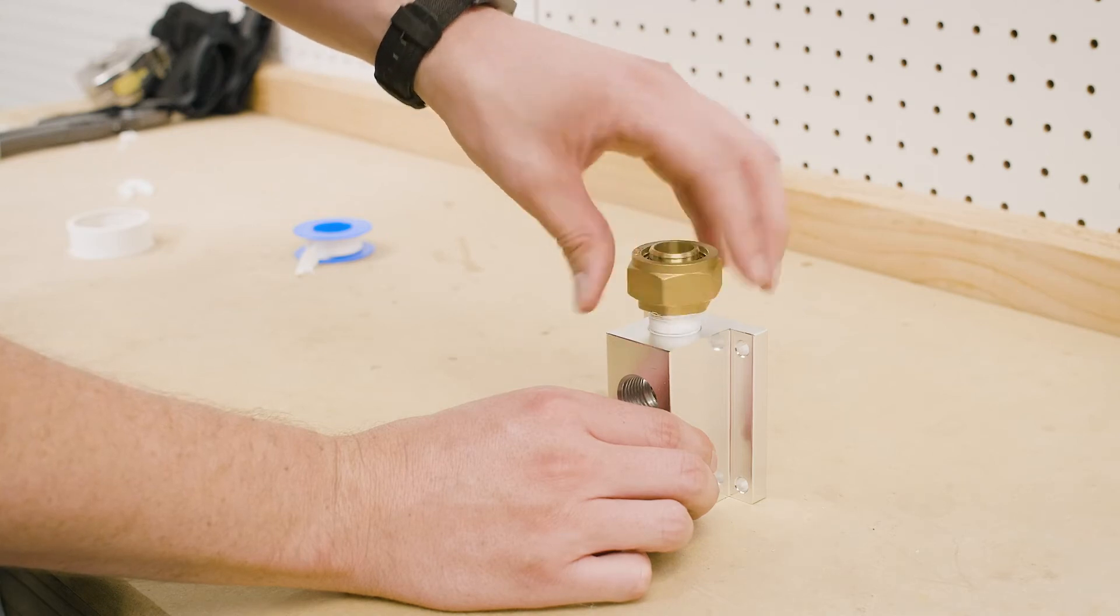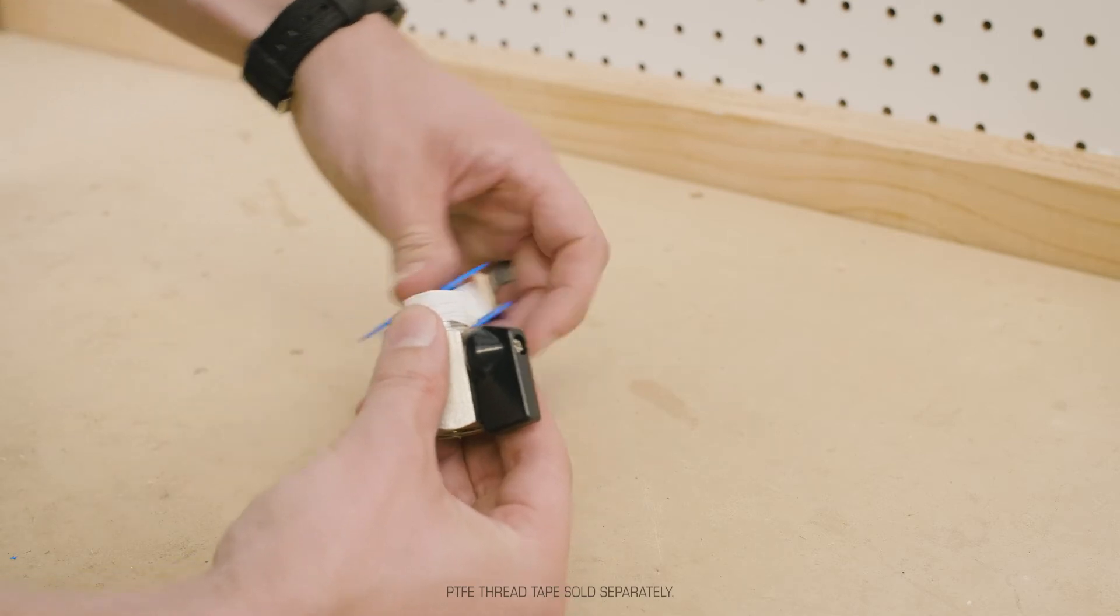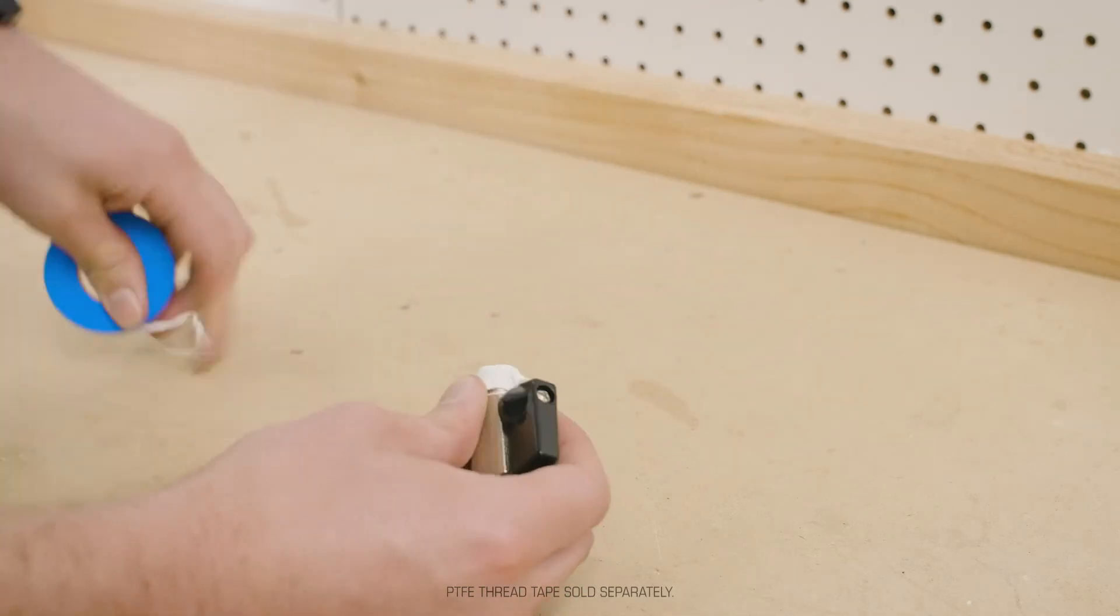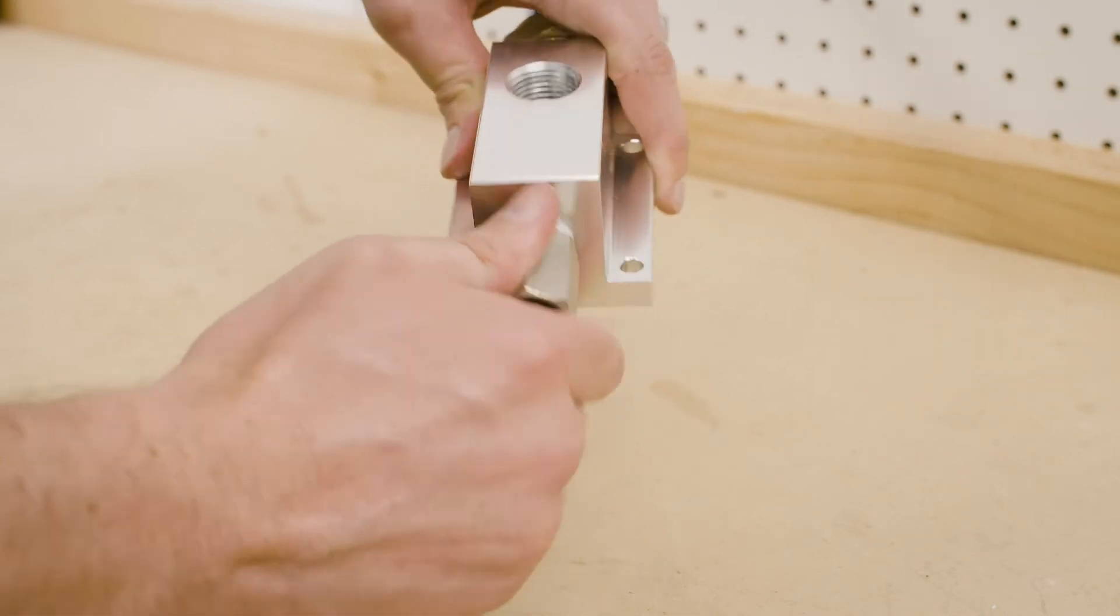Prepare the outlet you plan to use as an air source. Note, be sure to use thread sealant tape on all NPT threads where they connect to the outlet manifold. Install a drain valve on the opposite side of the manifold and tighten securely.